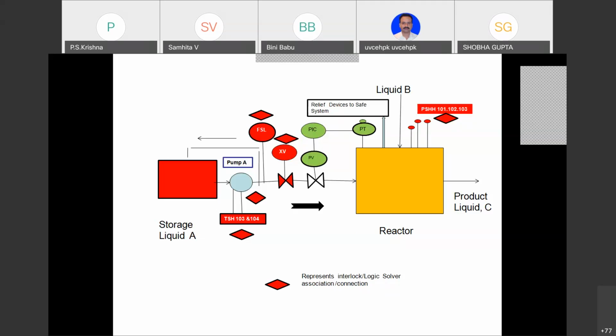That logic controller could be a PLC, it could be a relay circuit, whatever, and that will give a signal to this red valve called XV and shut it. So now we have established that you need to have an independent pressure switch connected to a logic solver, which is a PLC or a relay panel or whatever you call it, and then the output goes and tells XV, please shut.